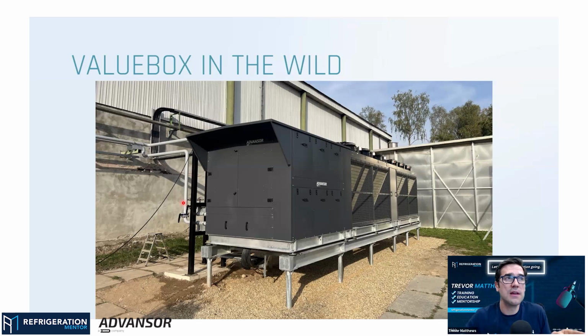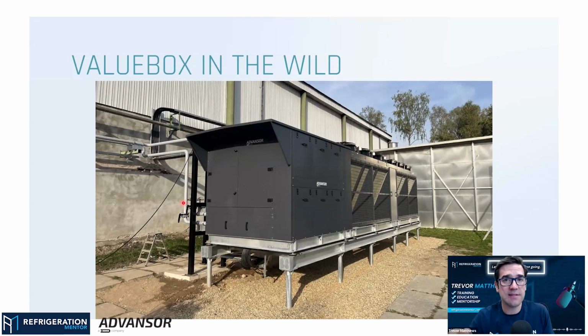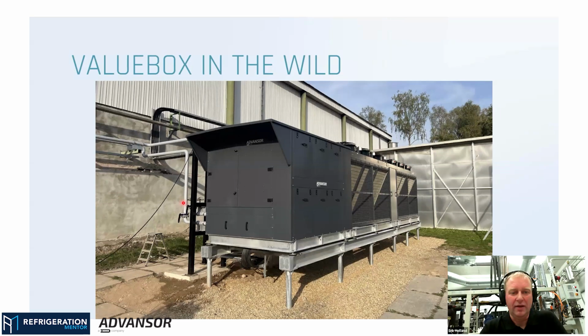And so I would think it would be taking the inlet and outlet water temperatures, how that is affected, right? Because now that compressor, we're going to have to change capacity. So depending on what my inlet water temperature is, will depend on how I need to run. And depending on my outlet water temperature, how much heat are we pulling out, or how much heat do we need. Yeah, exactly. So it is controlled by the water temperature, because the customer is buying a water temperature at a given flow. So many kilowatts at this temperature.